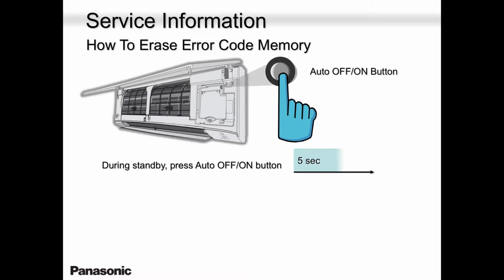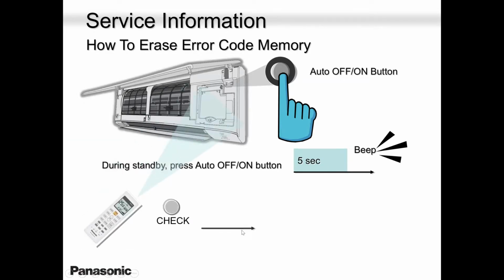Okay, after you erase the error code, guys, it's how you do it. You lift up the cover, you press the push button over there, which we call the auto on and off. Once you hear one beep, you go to your remote controller and press the check button once. After you press once, you hear another beep, your error code is erased. Okay, guys?